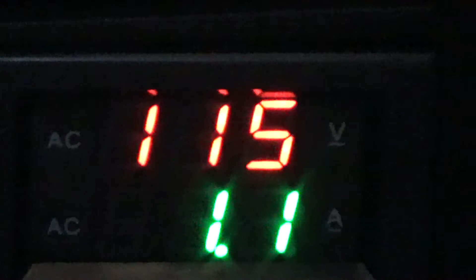If I turn it off, it's basically 1.1. First thing I would do is take a look at this converter to make sure it's not connected directly to the AC from the inverter—that it's isolated from the inverter. Most inverters don't have bypass switches or chargers built in like mine do. So I'd make sure this converter isn't hooked up to the output of the inverter—that's number one. I'd also make sure the converter in this box is wired correctly.